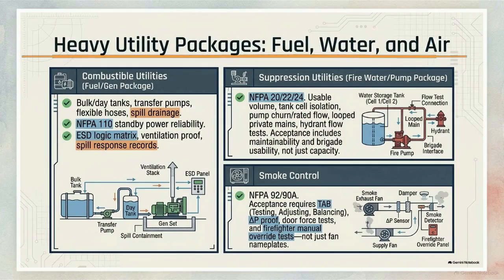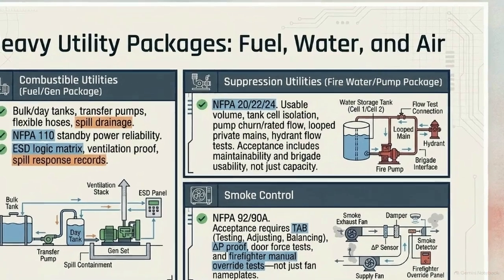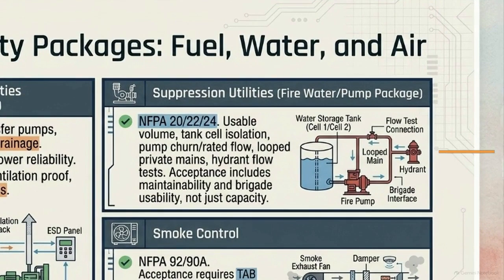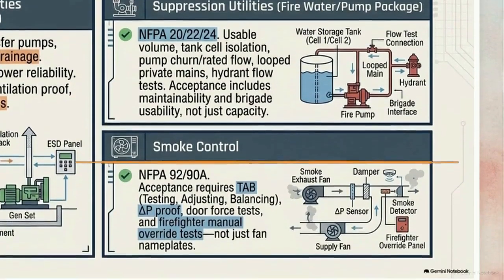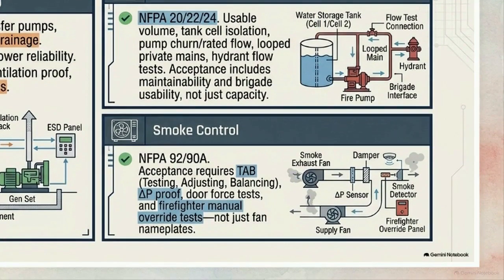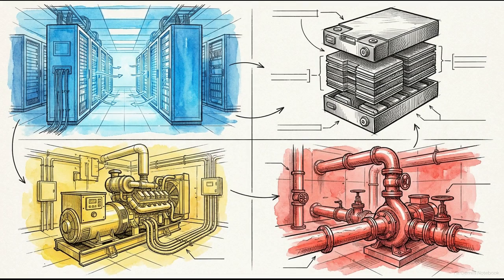Now look at the heavy utilities required to keep the facility running during a grid failure: bulk fuel, emergency generators, and suppression water supplies. Approving these suppression utilities requires verifying usable volume, hydrant flow tests, and physical interfaces for the fire brigade. The nameplate on the tank is only the starting point. The same rigor applies to smoke control. Acceptance demands physical proof of pressure differentials across doors and functional tests of firefighter manual overrides. The data center operates as a collection of distinct volatile microenvironments. Each one demands uniquely verified physics and testing protocols.